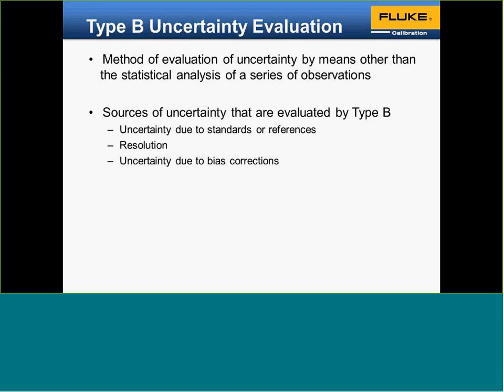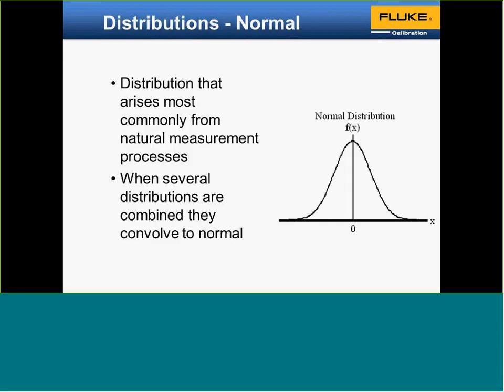Type B evaluation is a method of evaluation by means other than the statistical analysis of observations. It can come from the uncertainty of standards used, from the calibration report, or from the known resolution of the item. Corrections are used as a type B uncertainty. Distribution, bell curve.